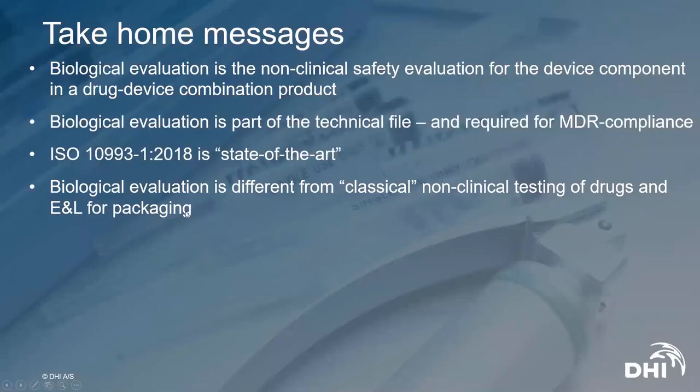For biological evaluation, you should remember that it's different from the typical non-clinical testing of drugs and extractable and leachables for medicinal packaging materials. So there may be some endpoints that you cannot address by the non-clinical testing on the drug.